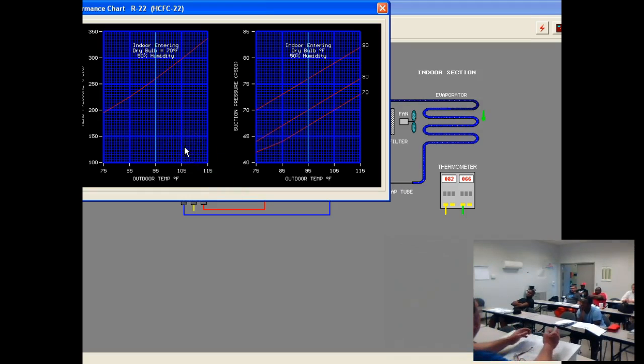These tell you, given the outside temperature and the inside temperature, what the suction pressure should be, what the discharge pressure should be, okay? So you could go, well, I don't know if it's high or low. Well, you come here and you can check it, right? It says right here, I don't know if y'all can read it from back there, my indoor entering dry bulb, 70 degrees. So I have a red line that runs up at 70. Well, down here on my stats, my indoor temperature is 81.